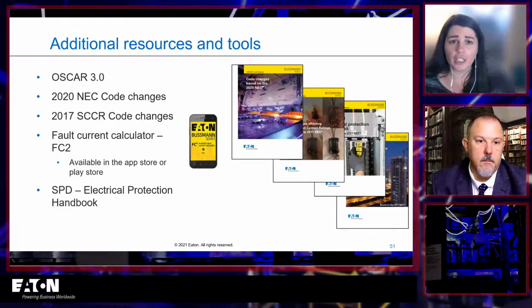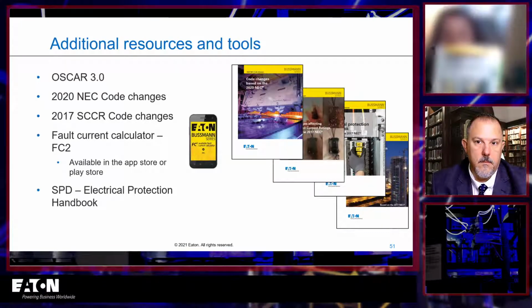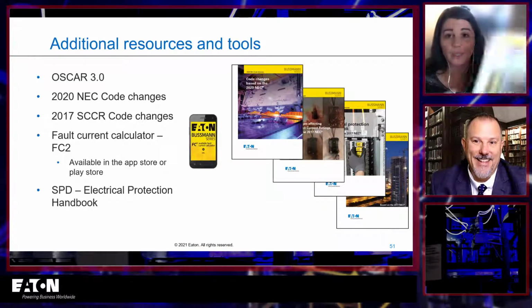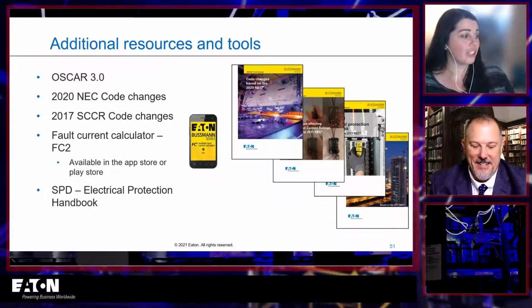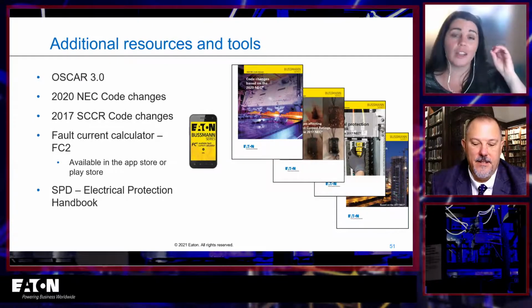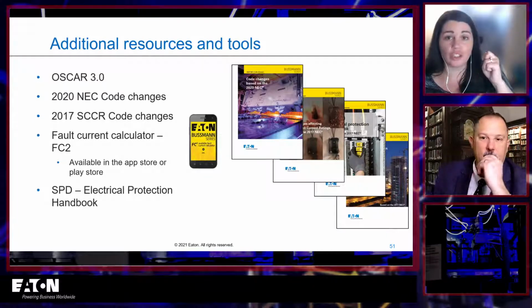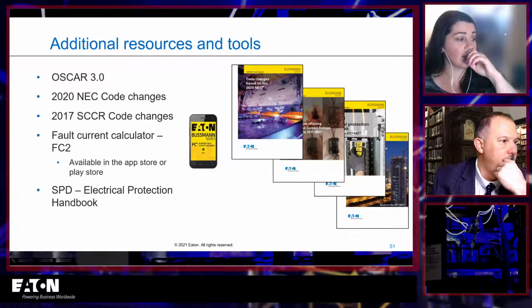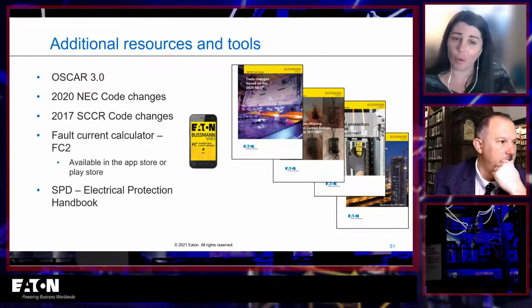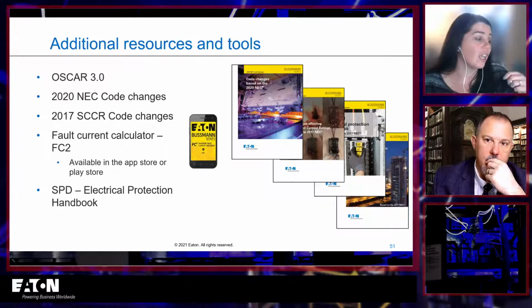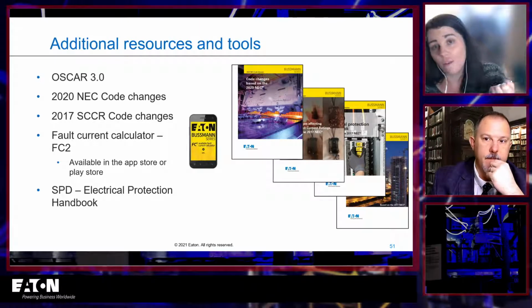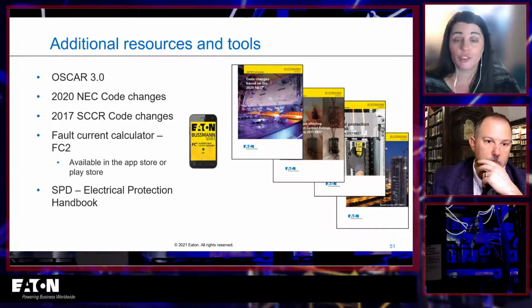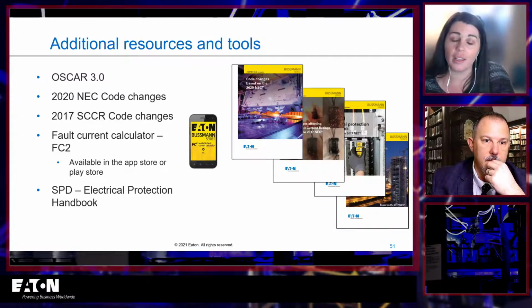And then the SPD Electrical Protection Handbook, if you've never heard of that, another amazing one. I have mine. I always keep mine right next to me. There's a million tabs in it. There's thousands of coffee stains and rips and tears because I use it so much. It's the Electrical Protection Handbook, and it has so much good information. It has some current limiting charts for fuses in there. It has voltage drop calculations, the long form way to do fault current calculations. It has all of those tables and charts that you need for UL 508A. It tells you how to size a fuse for a transformer, medium voltage, low voltage, and everything in between. So it's a really handy handbook, and it's also available online.